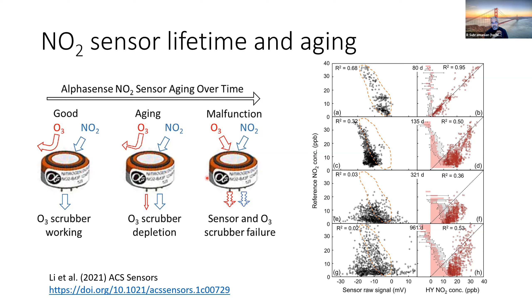At this point we say that these electrochemical sensors, in areas where ozone concentrations are relatively high like Pittsburgh—where you might see 70, 80 ppb periodically—you should change the NO2 sensors every 6 months, or at least every year in places like Kigali, where ozone concentrations are more moderate.